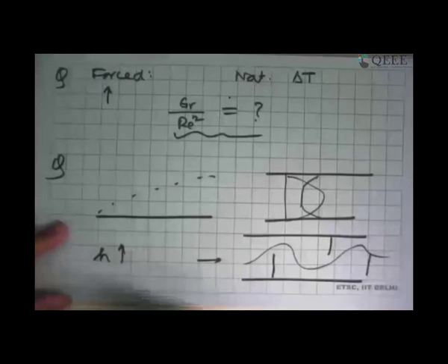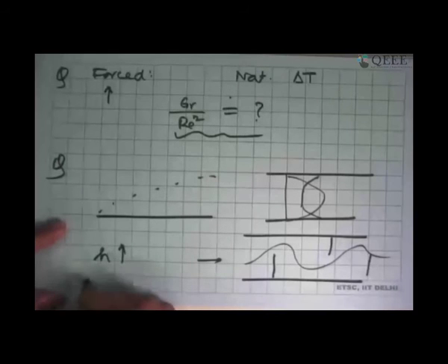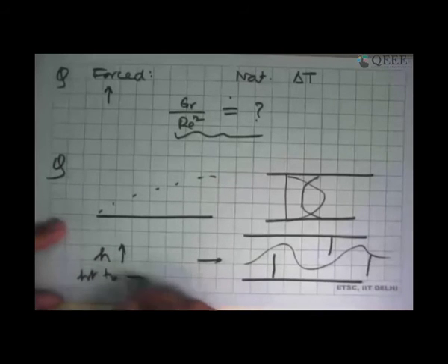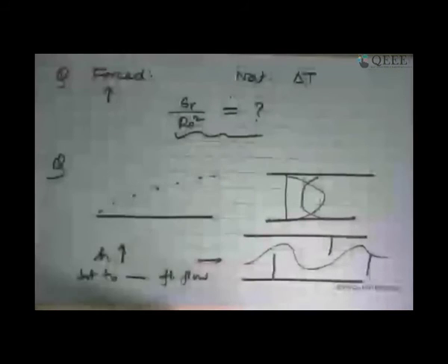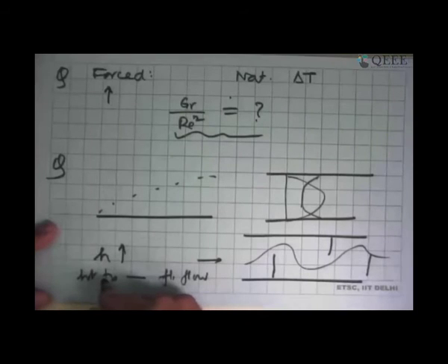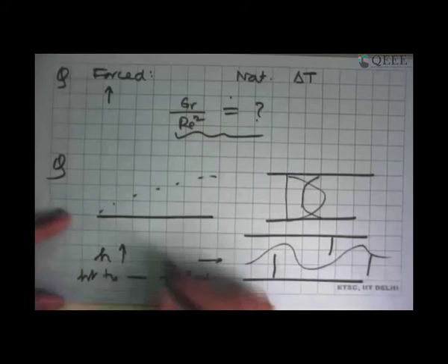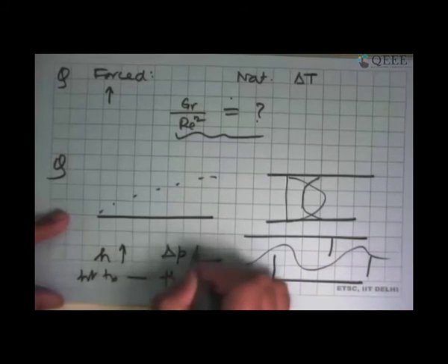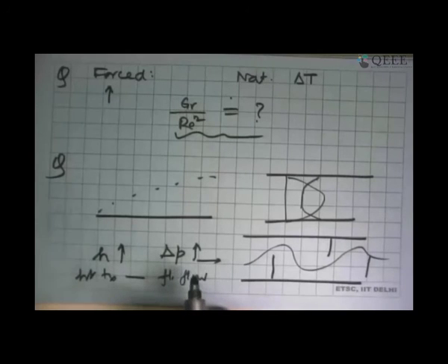But the important thing here is that in all heat transfer equipment design, the heat transfer problem and the fluid flow problem are strongly connected. When you do something like this to increase the heat transfer coefficient, or you make grooves here or roughen the surface, the heat transfer coefficient goes up, but so does the pressure drop. Which means that the pump or the blower which was establishing the flow now has to do more work.